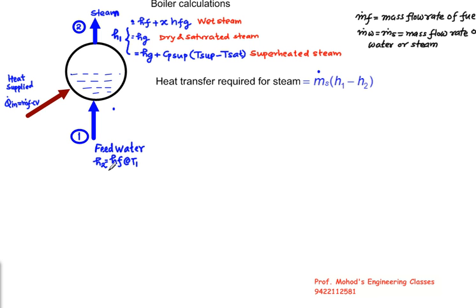Feed water is supplied at temperature T1, so H2 will be equals to HF at T1. Steam form may be wet steam, dry steam, or superheated. If it is a wet steam, then H1 will be equals to HF plus XHFG. Dry and saturated will be HG, and superheated it will be HG plus Cp sup Tsup minus Tsat.